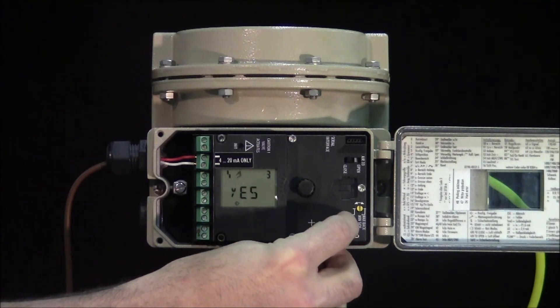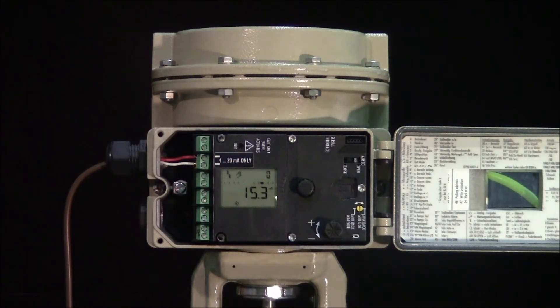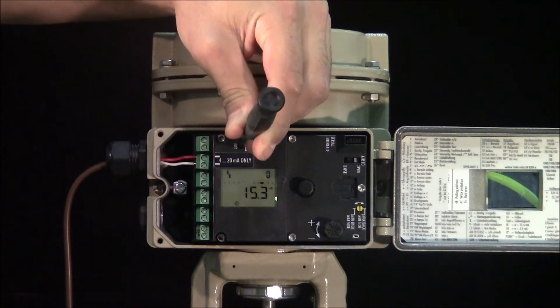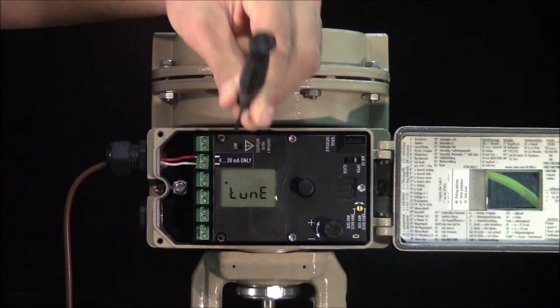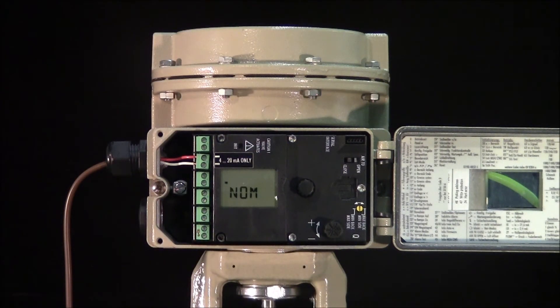We now go back to parameter 0 and press the recessed initialization button to begin the auto-calibration process. This process can take a few minutes while the positioner adapts itself to this specific valve and its operating characteristics. It's important not to disturb or interrupt this process until it's finished.